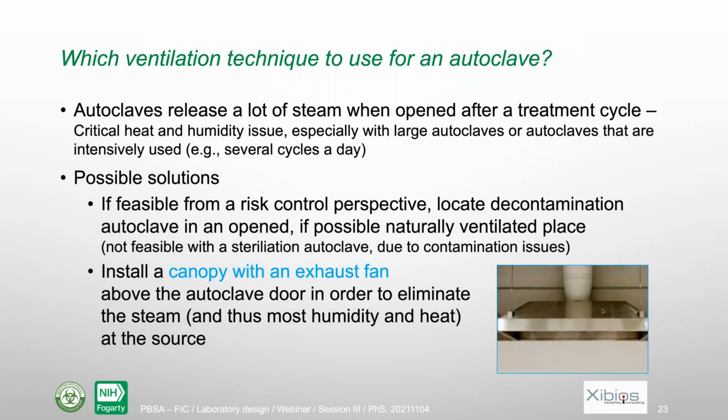And this is really an issue if it's present in a lab. So with respect to ventilation, there are different possible solutions. If it's a decontamination autoclave, it could be in a rather open environment, which is not very ventilated. Of course, if it's high risk biological waste, and if you don't want to take any risk of spreading the material, in that case, that solution is not acceptable. It's not good for a sterilization autoclave either, because you want to have your material sterile when you get out of the autoclave. But in other situations, you can have it in a quite open environment so that it's naturally ventilated. That's the easiest and most affordable solution.